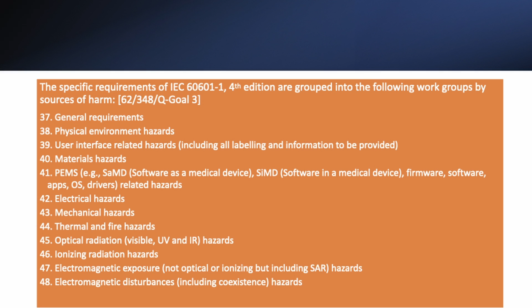Mechanical hazards will be revised to be state of the art. Same with thermal and fire hazards. We'll be looking into additional optical radiation hazards from visible, UV, and infrared light sources that can cause harm to biological tissues, patients, or users. Radiation hazards such as X-ray will be covered to some extent, leading to the particular standards developed in 62B and 62C. Obviously, 60601 has not addressed electromagnetic exposure for specific absorption rate and other EMF exposures. And then the EMC sections are covered in electromagnetic disturbances.